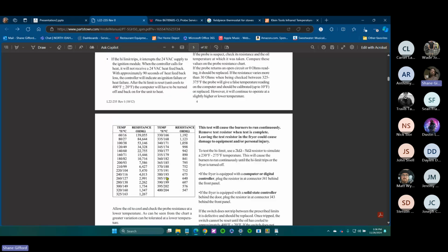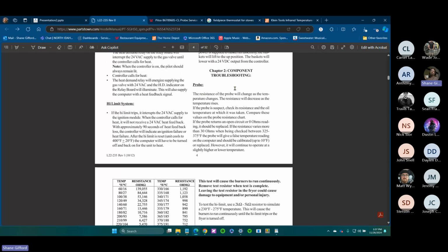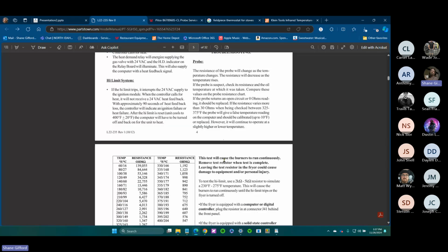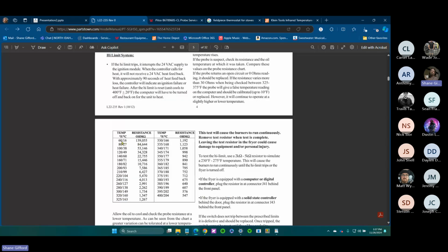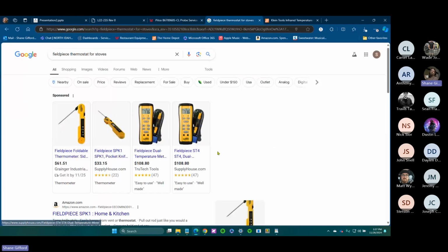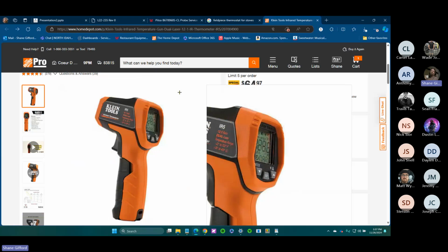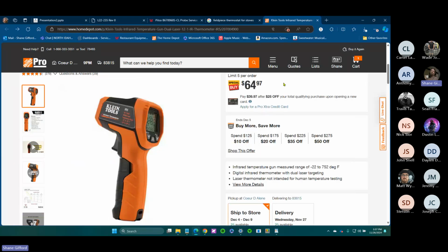But right here, I don't recall which sensor this one is. High limit probe. Okay, so it's got component troubleshooting, and it'll always tell you temperature and resistance. So if you've got a good means of proving your vat temperature, let's say you're using an infrared gun like this one right here, I personally use this one. It's $65 at Home Depot. It's good up to 752 degrees.